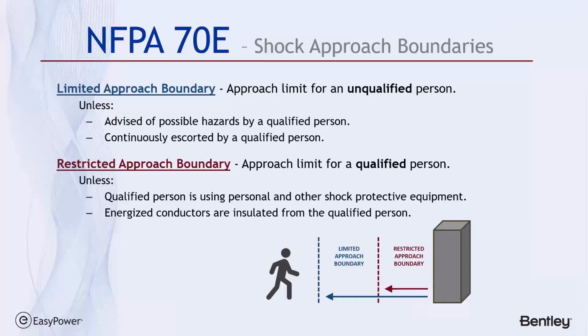And then the closer-in boundary is the restricted approach boundary, and it's the approach limit for a qualified person unless the qualified person is using PPE and other shock protective equipment, and the energized conductors are insulated from the qualified person. So again, these are based upon voltage, and they're fixed numbers, fixed boundaries based upon the voltage that's being exposed.